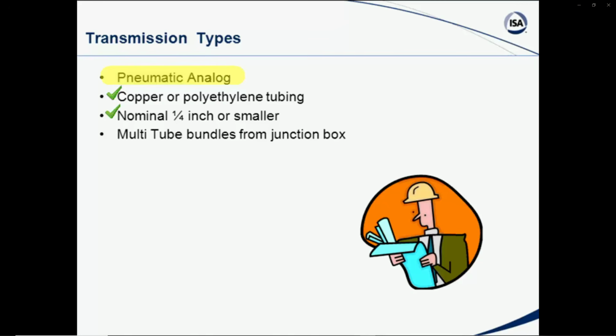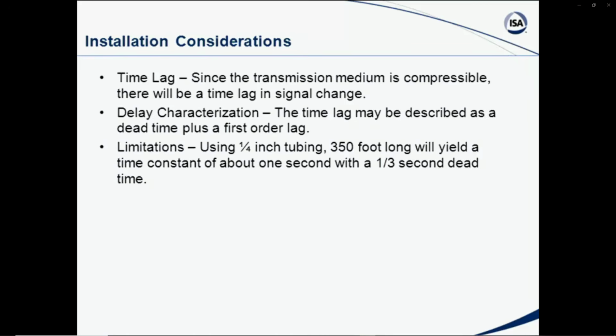But these also become part of the characteristics of the overall dynamic response of a control loop, as an example. So we need to be aware of that. There are multitube bundles that are run many times from the junction boxes back into the control rooms, but also there may be a multitude of pneumatic controls in an area, or you may be involved in a facility that has a lot of pneumatically actuated valves or other types of dampers or drives. So we have to be aware that pneumatics still exist, are still part of many units, and there are some considerations that we should take into account.